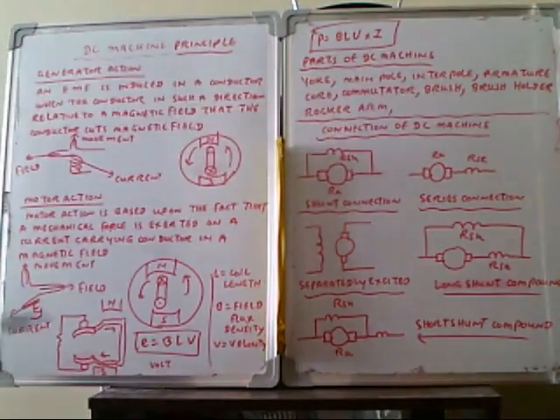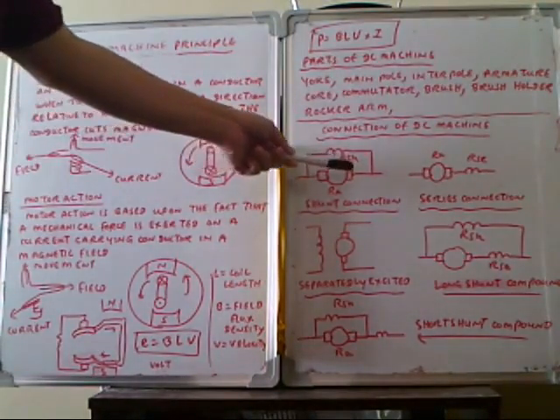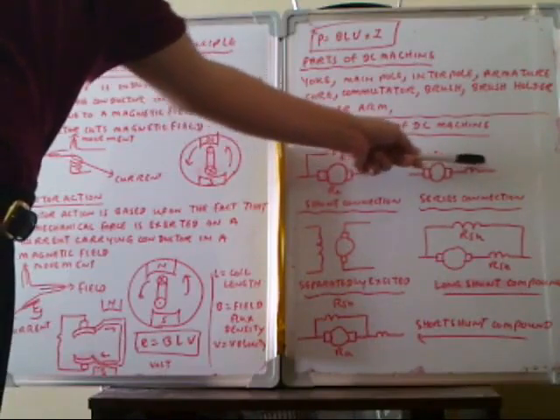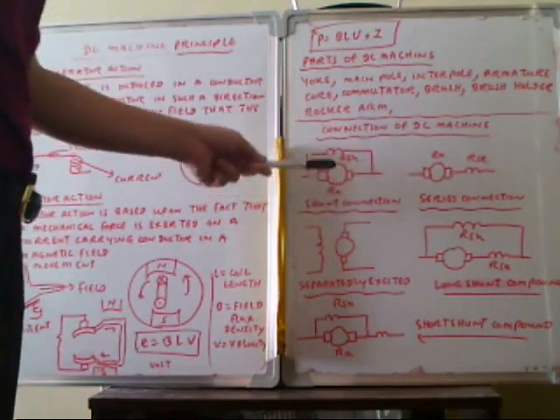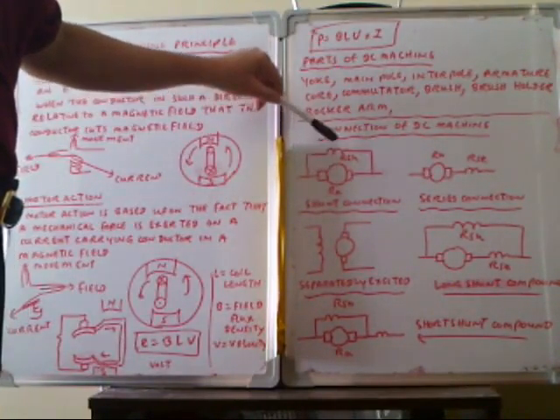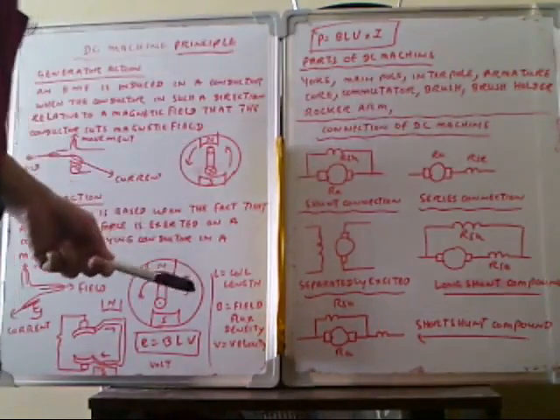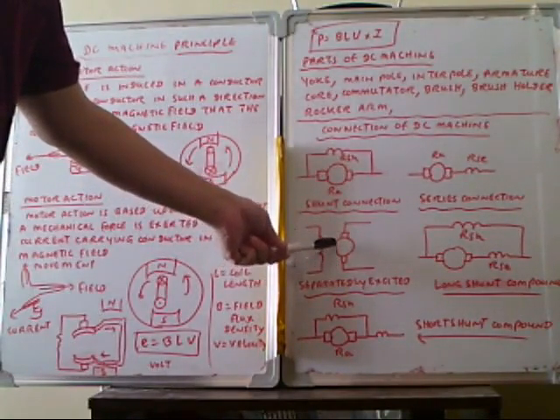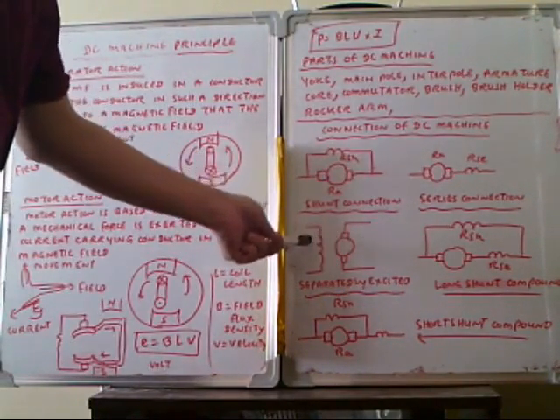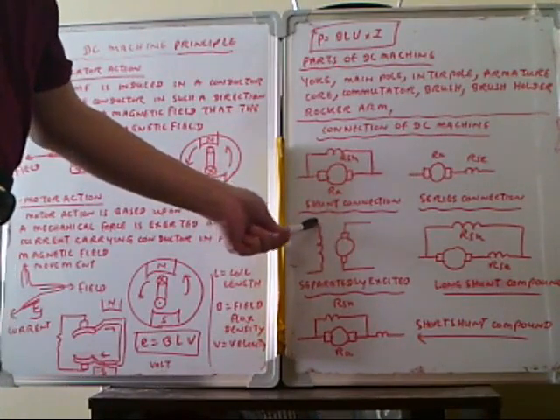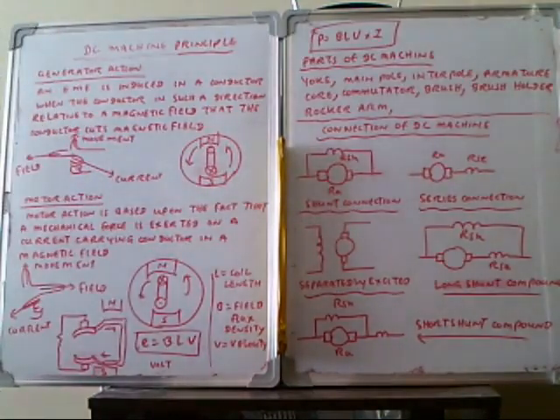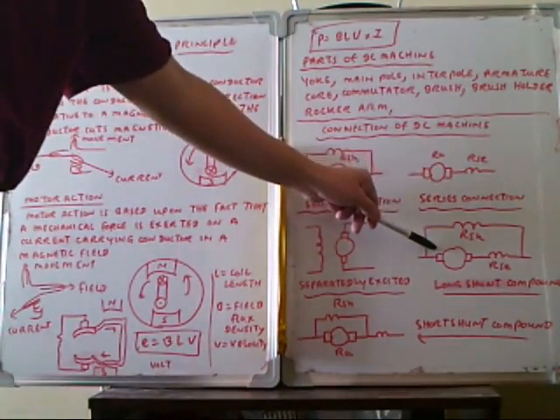This is the shunt machine, where the armature R_a and shunt field R_sh are connected in parallel. For the series machine, the armature R_a and series field are connected in series. This is the separately excited configuration, where the armature winding and field winding are not electrically connected — the field is separately supplied by an external source.